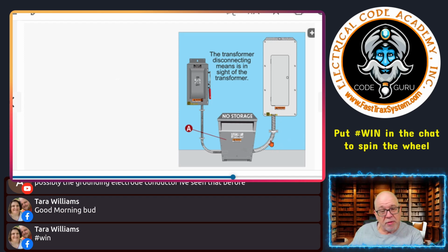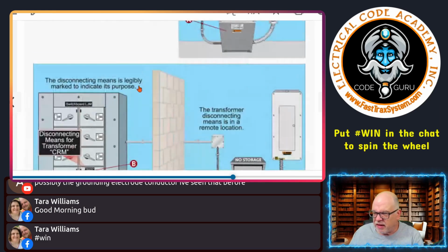Okay, but remember, the supply side bonding jumper is different than maintaining bonding requirements on something like an FMC, and doing a bonding of this product. Now, most people say, well, I'm going to get away with it by just simply doing a lay-in lug on each side and looping it through, and then they don't really have to do anything here, because they don't have to run a bonding jumper outside since the bonding is taking place. Okay, so again, it totally depends on your installation. We'll talk about that maybe in an upcoming episode because I can see where that could be confusing for folks.